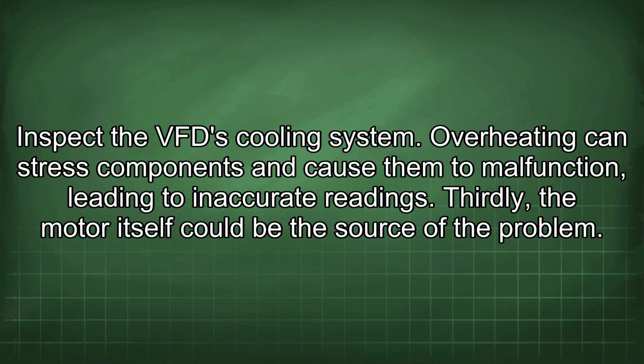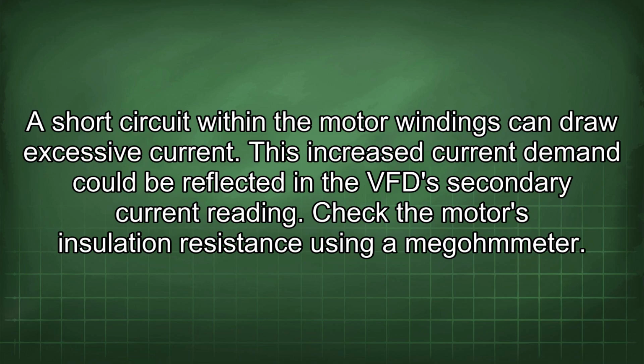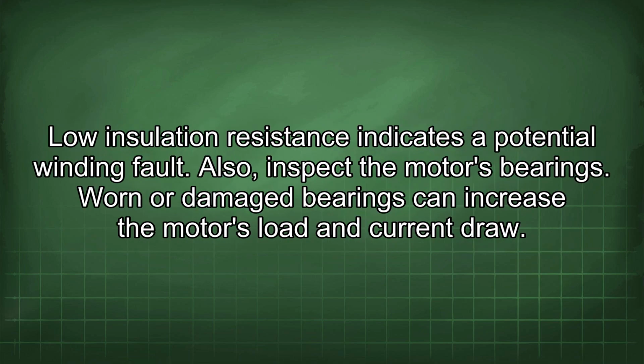Thirdly, the motor itself could be the source of the problem. A short circuit within the motor windings can draw excessive current. This increased current demand could be reflected in the VFD secondary current reading. Check the motor's insulation resistance using a megohmmeter. Low insulation resistance indicates a potential winding fault. Also, inspect the motor's bearings. Worn or damaged bearings can increase the motor's load and current draw.